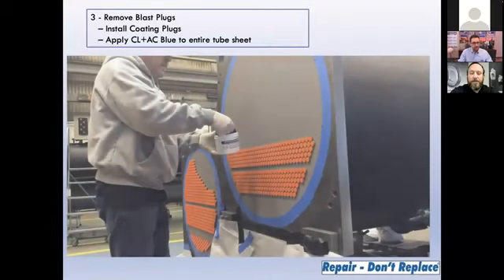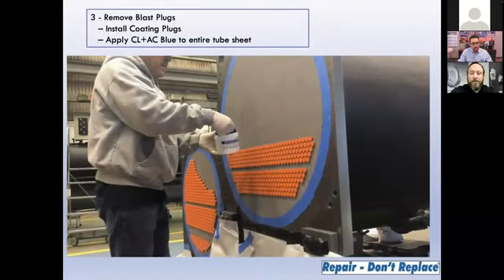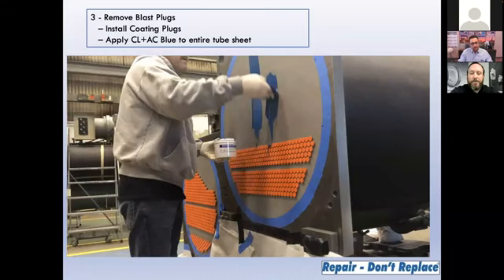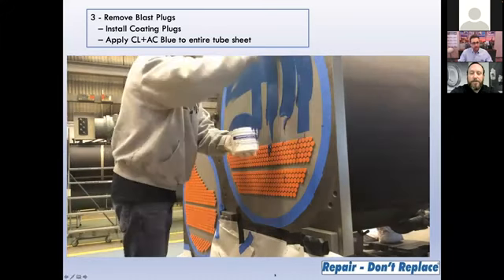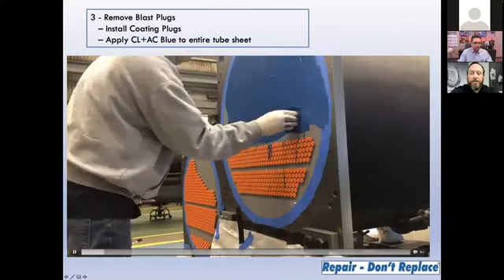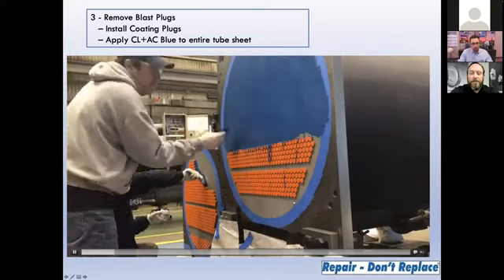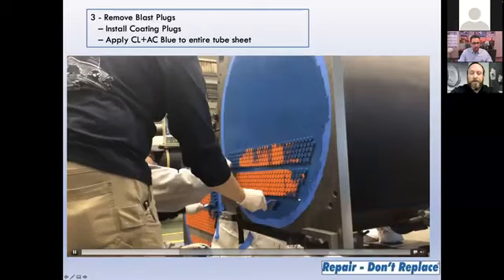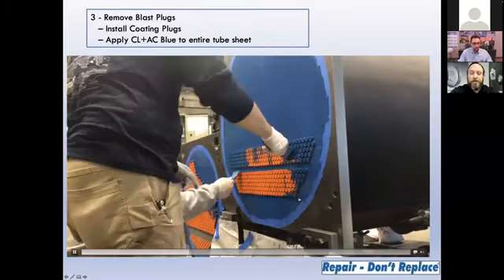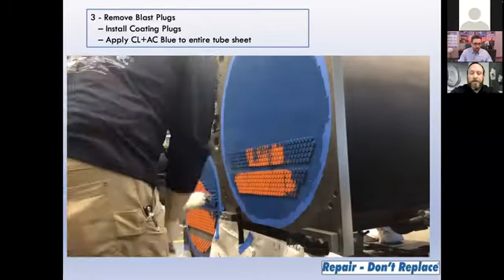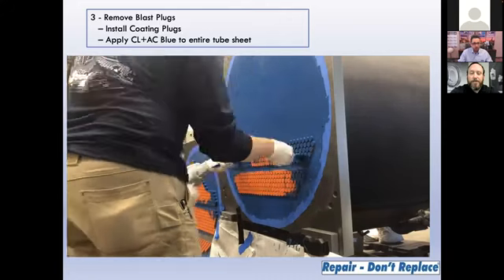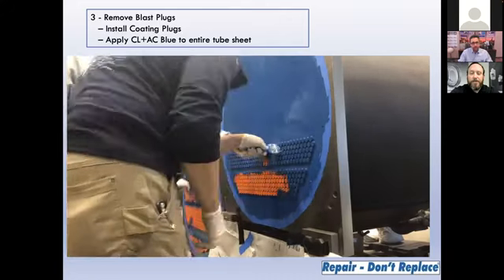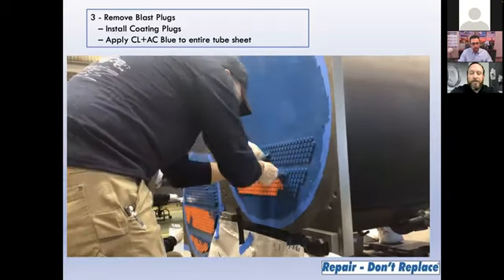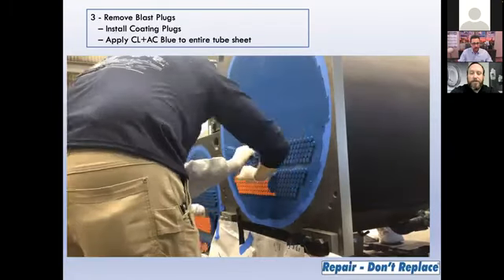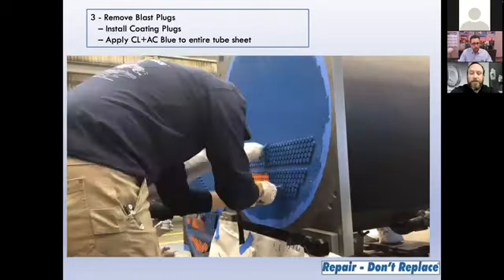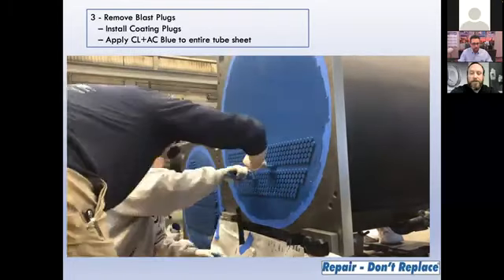The next part of the process is to remove the blast plugs, install protective coating plugs, and begin the actual application of the first coat of the Ceramaloy CL Plus AC Blue to the entire tube sheet. You'll notice in this video segment that the CL Plus AC Blue was first applied by an applicator, and then using a stiff bristle brush or a cut down brush, it's firmly pressed onto the substrate, paying special attention to the areas in between the tubes to make sure we get the proper bond in those areas.